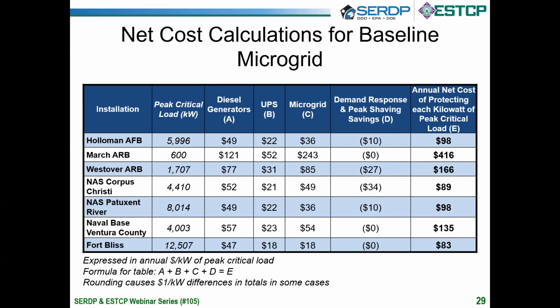So it's important to see, in doing so, can they reduce the diesel generator costs or the UPS costs? Can they increase the demand response or peak shaving savings? And can they introduce new savings from shifting time of use energy consumption patterns or from wholesale electricity markets like frequency regulation while meeting or bettering the baseline reliability requirements that Jeff discussed? That's the standard, the baseline standard they had to beat. Let's turn to the next section to see. Please go to slide 30.